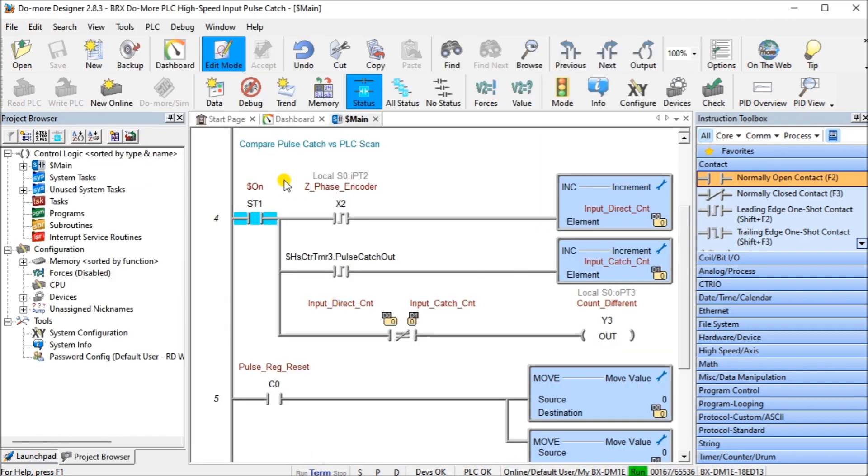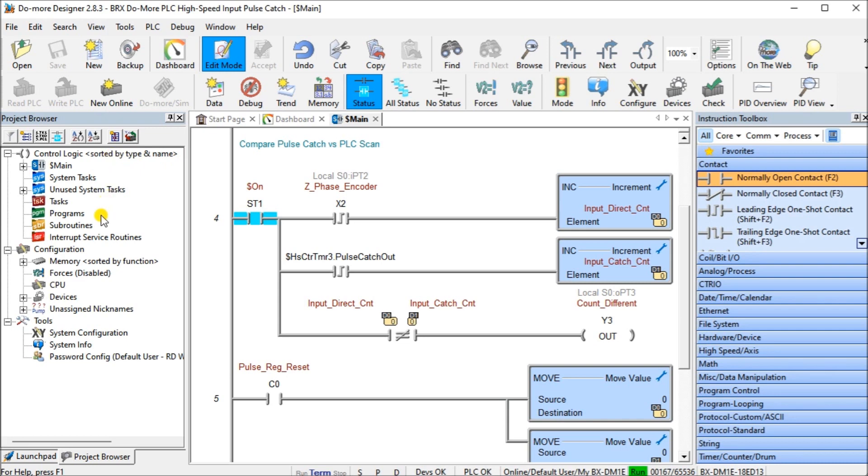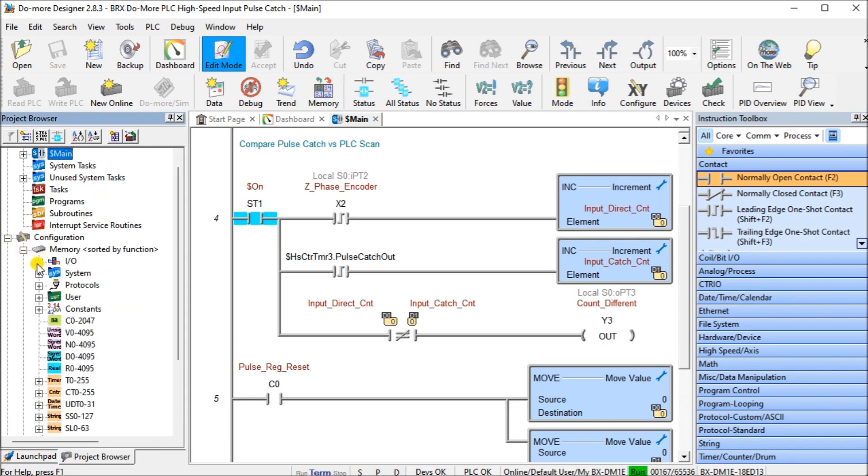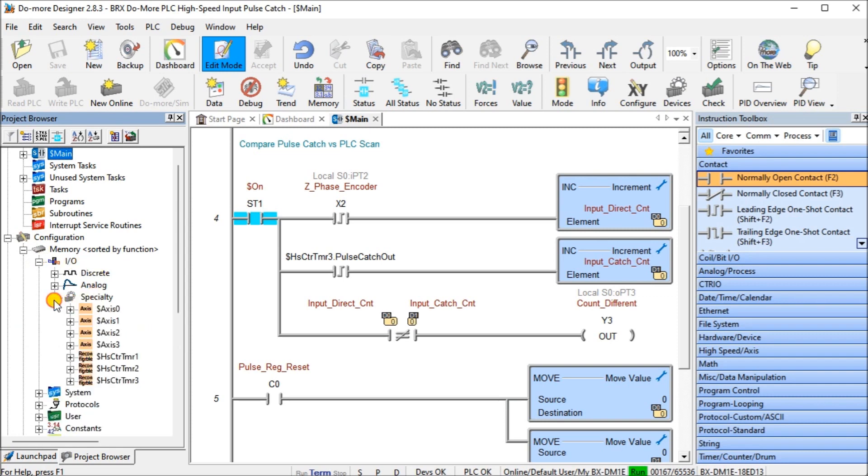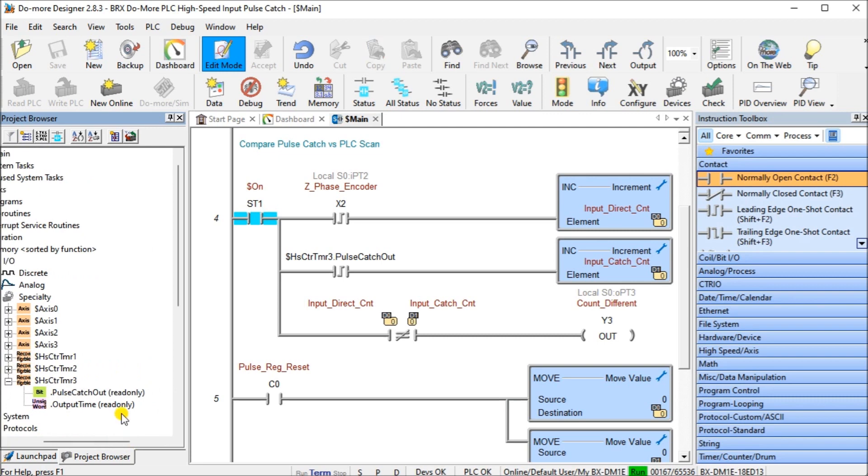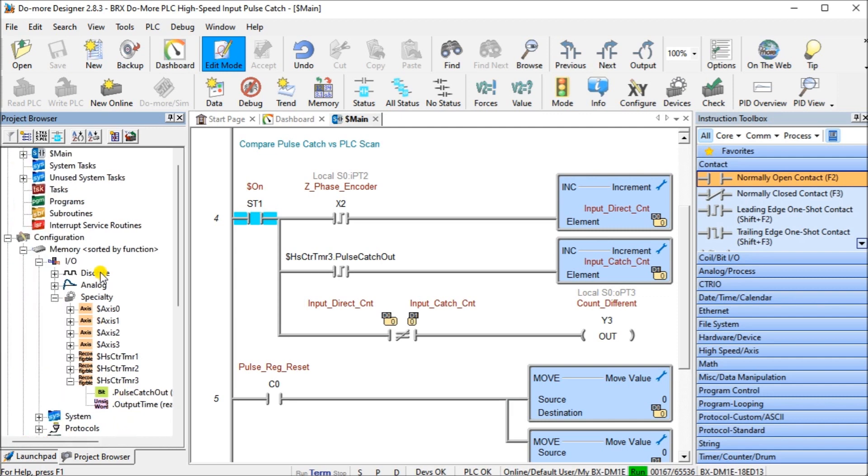Once we have that configured, we can then download this configuration into our controller. Remember when we set up the high-speed input, we also have this function name. So we go to configuration, under memory, under IO, and then specialty IO. You will see that high-speed counter timer 3 is now programmed. All we have is our bit saying pulse catch output, and then we have our output time. That's available if we're going to do a time sequence on that. It's going to read that input pulse bit. That's the one we want to pick up in our program.